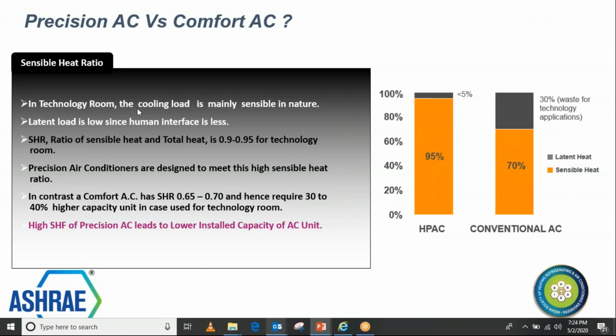And when you have electronics or electrical equipment involved in your server room or a control room or VFD room or any such rooms, it is only the equipment which is present there. When you do load calculation, you are actually supposed to get 100% sensible cooling. Sometimes maybe some people are sitting there, like in a control room you may have a few people sitting, and the outside air which is entering there as fresh air. When you put this together and do the load calculation, you will typically find that the sensible heat ratio for all these kinds of applications is more than 0.9, or 0.95. In fact, sometimes it goes close to 0.98 or even 1.